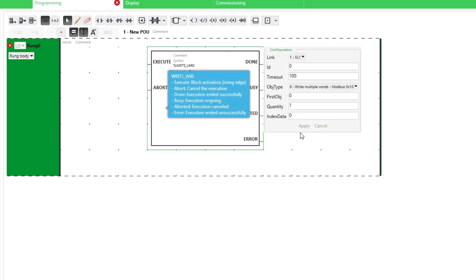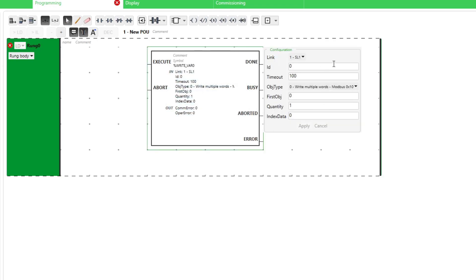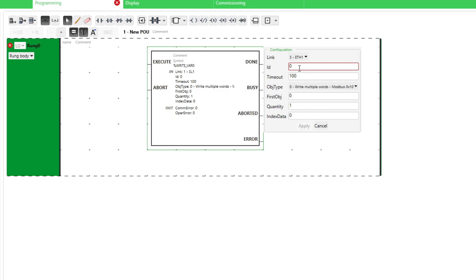If we hover the mouse on the function block a configuration menu will pop up. Here we want to change the link to Ethernet port 1. And the ID is which Modbus ID we want for the client, I will go with ID number 1. The timeout I will leave as it is at 100.